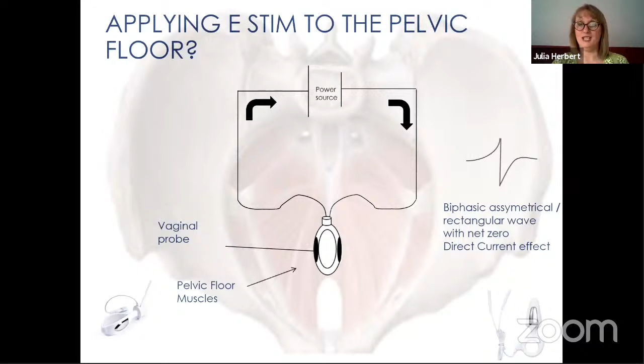So we've got a power source in the middle. We're actually sending a circuit of electrical energy out through one of the stainless steel plates, through the muscles, and being collected on the other side and back to the power source. It's a biphasic asymmetrical rectangular wave, if we want to get into the physics of it, and it's a direct current effect because it's going round in the same way. But the energy is depleted because it's asymmetrical and it's biphasic. It's actually building up the energy and then it's dropping the energy down before it resets itself.